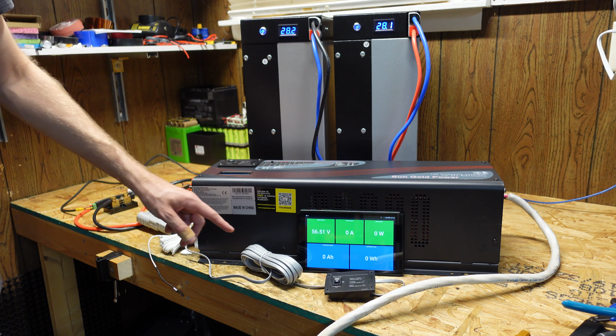Before we actually turn that on, I have my Batrium display here. We can see we're at 56.51 volts and it's zeroed out to 0 amp hours of capacity. So I'll go ahead and flip this switch to on. Alright, the inverter's turned on - you can see it's idling at 1.86 amps or 104 watts.